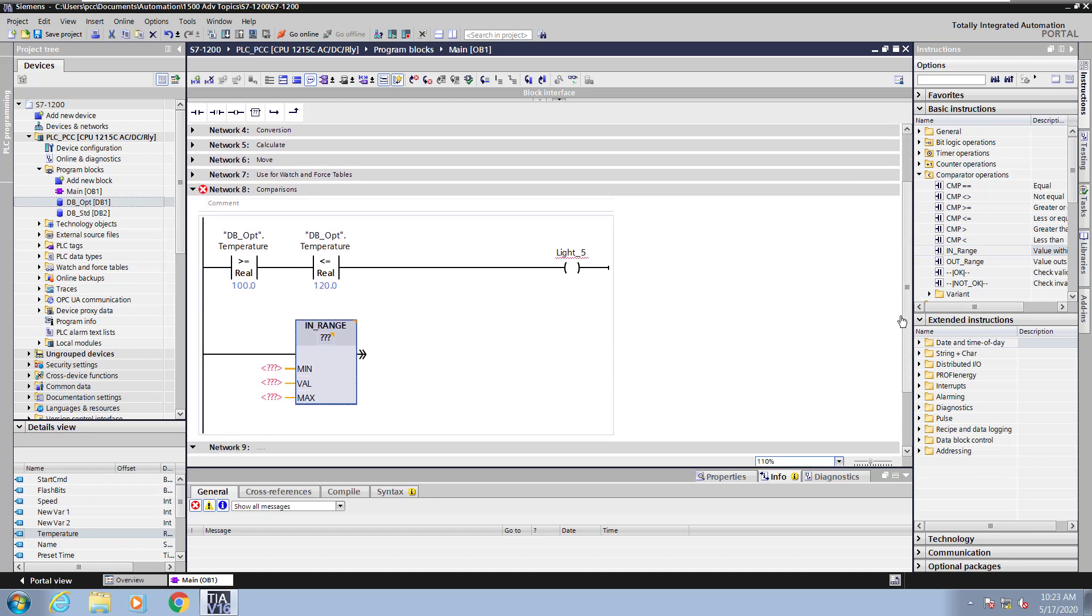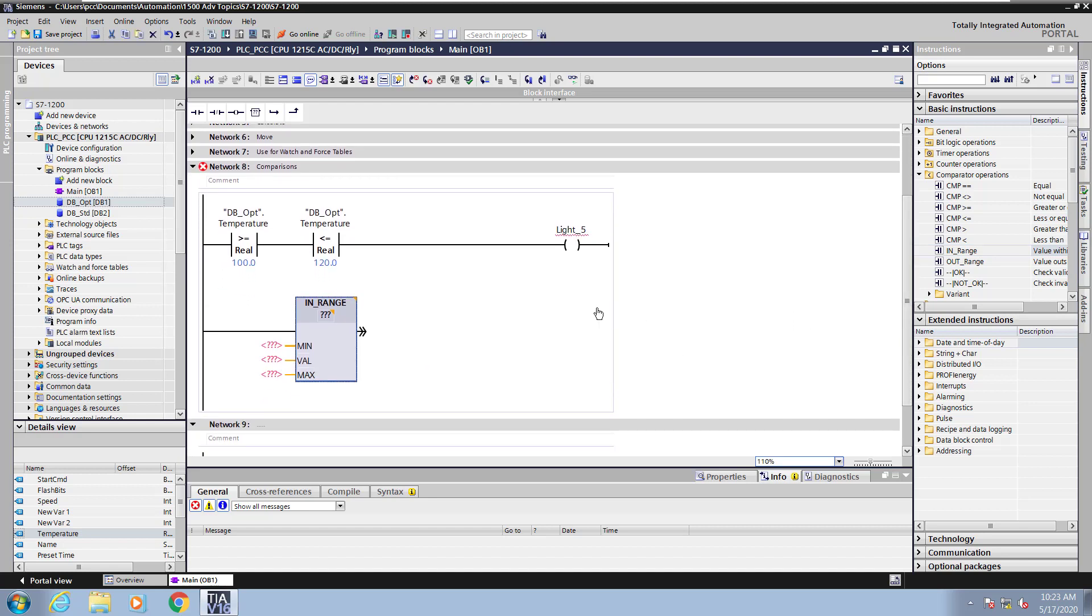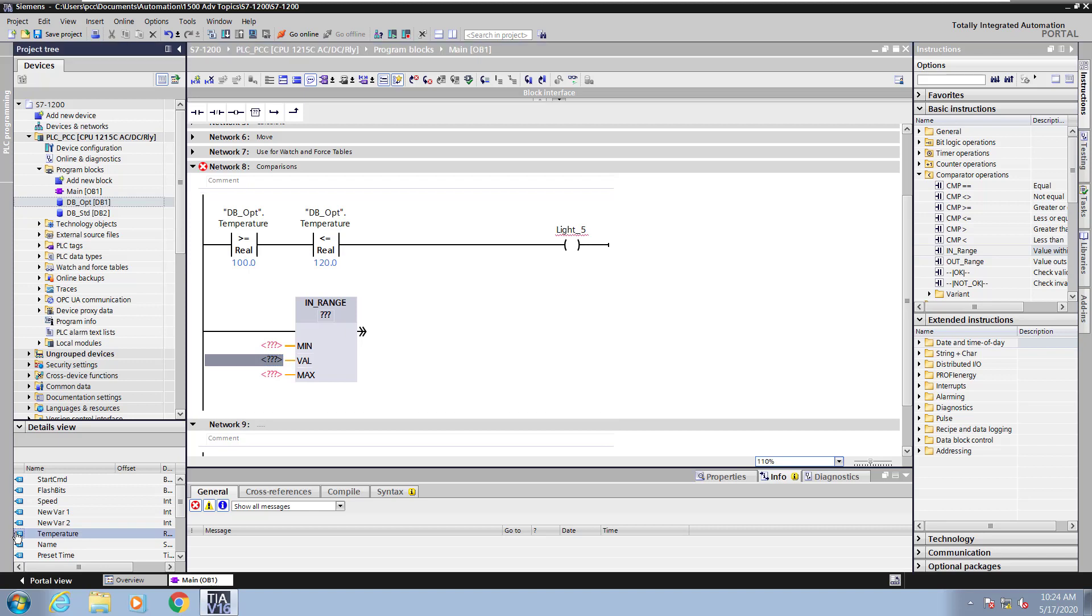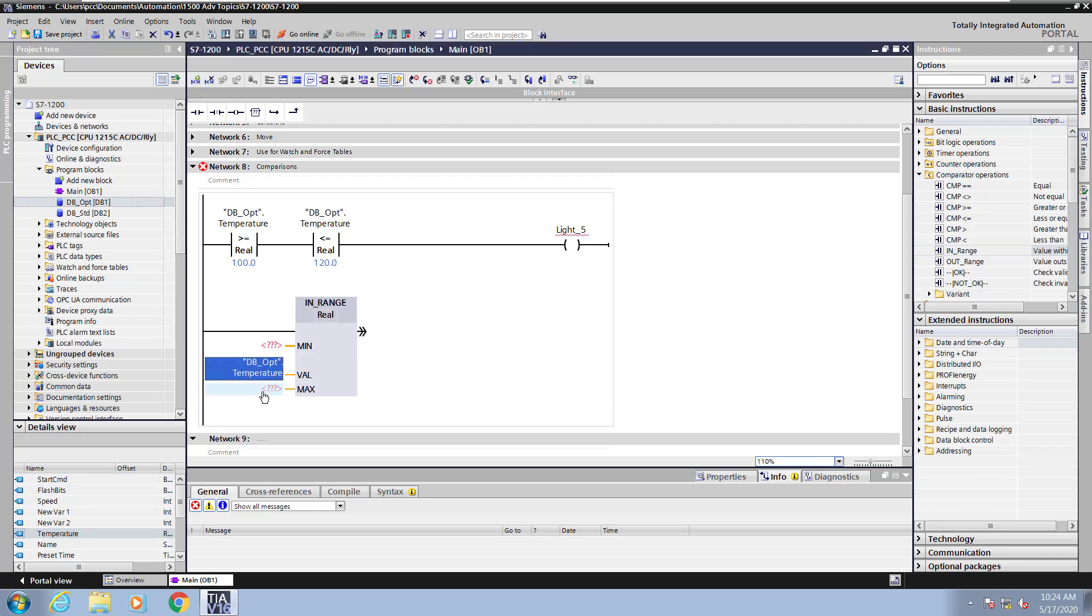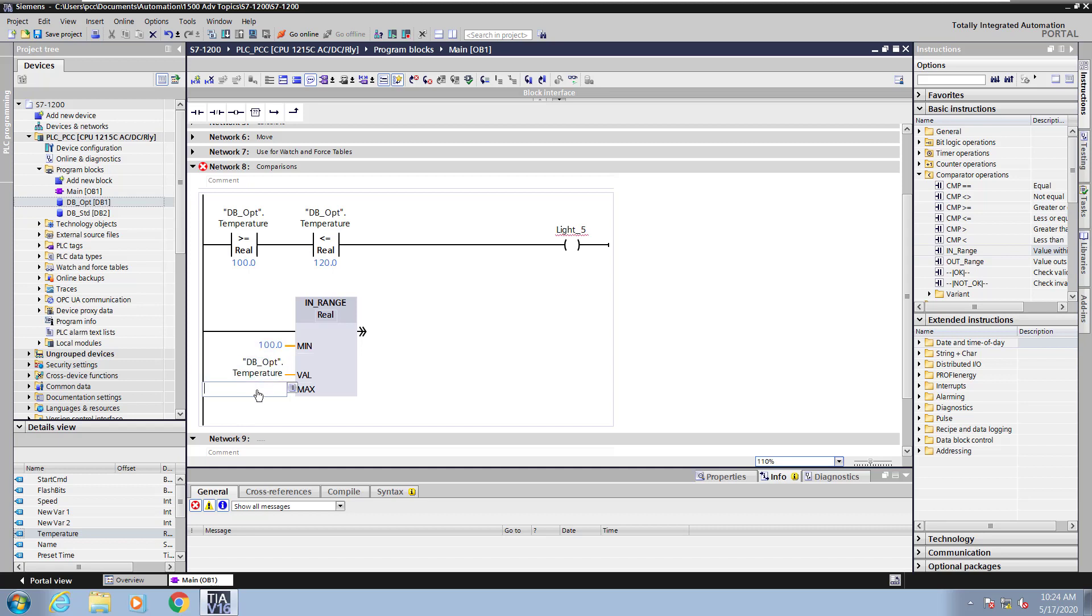I'll scroll down so that I can see all of my logic. So for the value, I will use the temperature value again. So I'll do a drag and drop from the details view to bring in the data block element to compare against. The min value, I will put in 100.0. And the max value, I will put in 120.0. So the temperature value has to be between 100 and 120 inclusive.